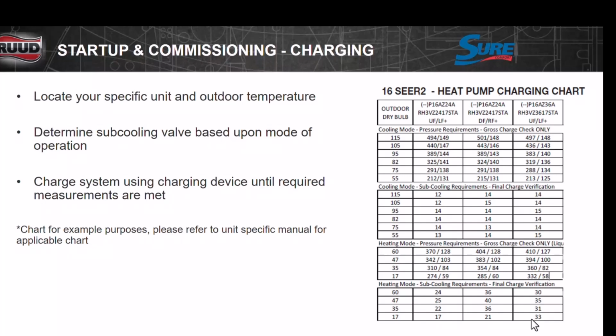82 degrees. This is a target of where we're going to be running. Of course, we know that it all depends upon the indoor temperature and stuff like that. But we all know in the summertime that can be a lot of difference when we first crank this thing up to charge it. So we've got to let it settle down a little bit, let it pull the humidity out, because a real wet coil is going to, the pressures are going to be different on a wet coil, because we're actually blocking airflow through the coil because of all the water on it.